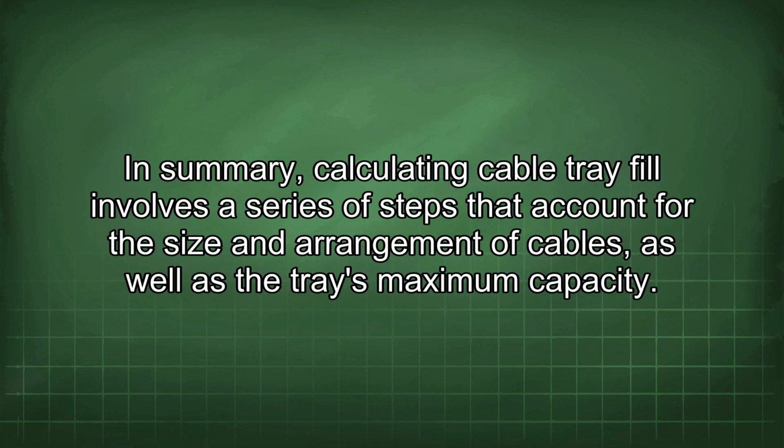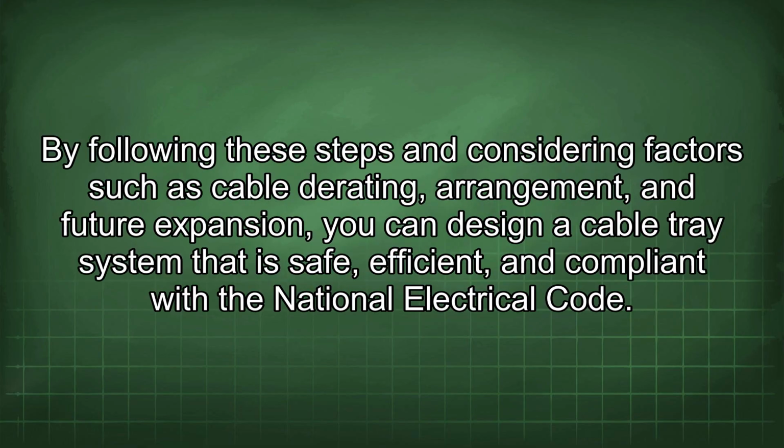In summary, calculating cable tray fill involves a series of steps that account for the size and arrangement of cables, as well as the tray's maximum capacity. By following these steps and considering factors such as cable derating, arrangement, and future expansion, you can design a cable tray system that is safe, efficient, and compliant with the National Electrical Code.